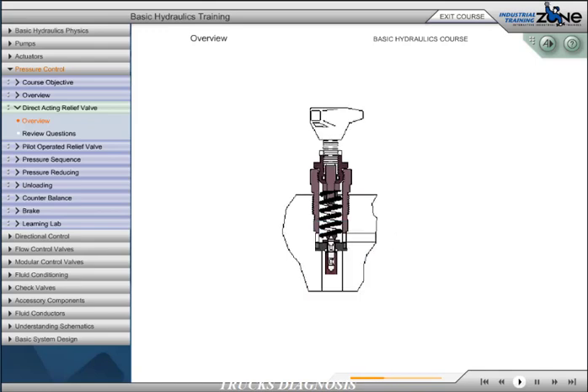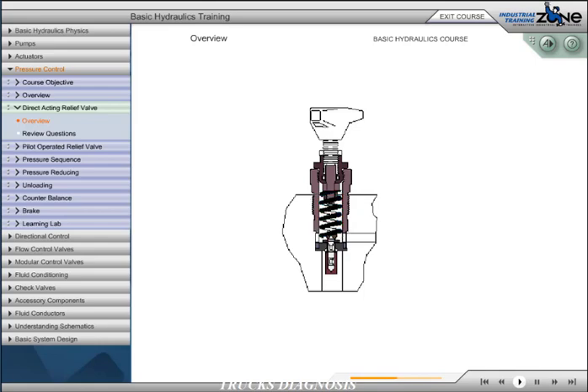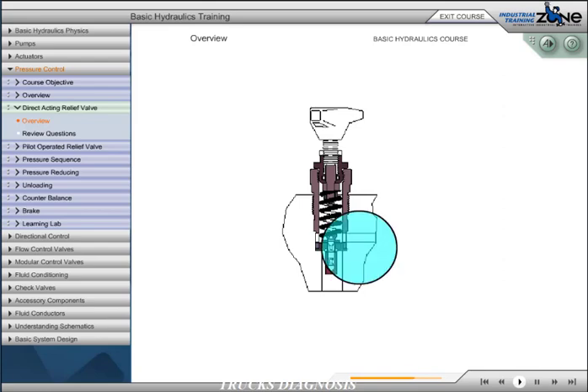A direct acting relief valve is one in which the poppet is held closed by direct force of a mechanical spring, which is usually adjustable. Spring tension is set to keep the poppet closed until system pressure reaches the desired cracking pressure. When the system pressure reaches full relief value, all fluid is passed to the tank passage. Direct acting relief valves are usually available in only relatively small sizes, because it is difficult to design a strong enough spring to keep the poppet closed at high pressure and high flow.